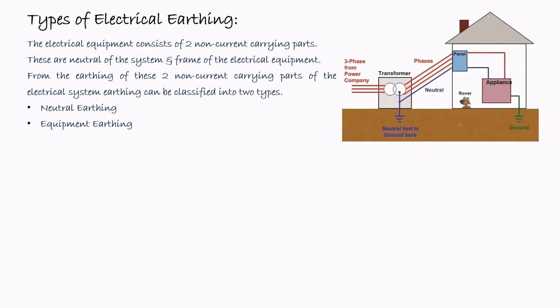So here we can see that in a particular domestic application, there is a transformer from where the power is supplied to this particular house. This is the supply system for this house, and here the neutral line is grounded, or connected to the earth. So this is considered as neutral earthing. Similarly, the appliances that are used within the house will also be connected to the earth through a common earthing terminal. This is considered as equipment earthing. So it is necessary to earth both the supply system, that is the neutral earthing, as well as the equipment earthing for full protection.